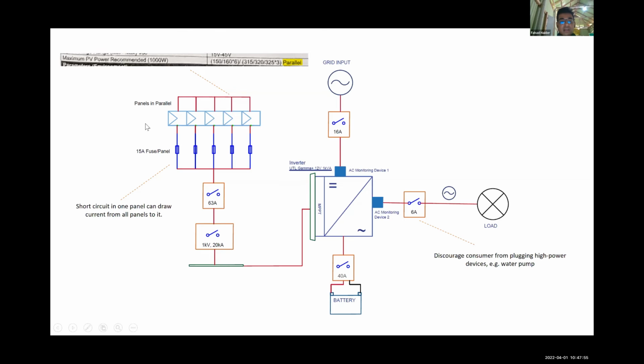I'll get a bit technical here. The VOC, and the ISC - the short circuit current from each panel is roughly 9 amperes. So 9 times 5 is 45 amps. So we don't expect it to go more than 45 amps. However, if there's something wrong with it, some short circuit or internal issue, in case it goes over 63 amps, that's why we put this circuit breaker.